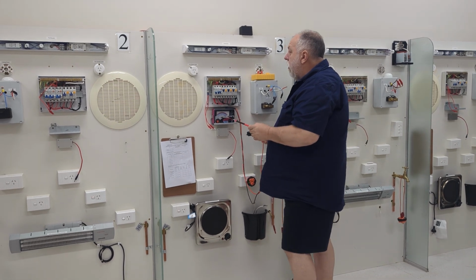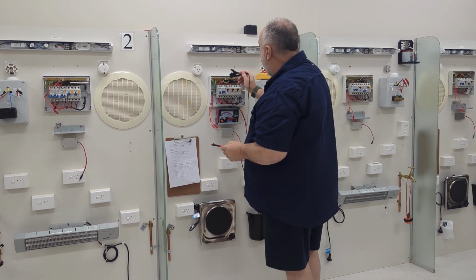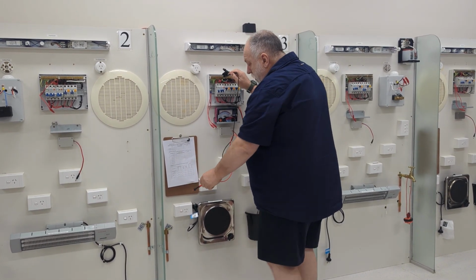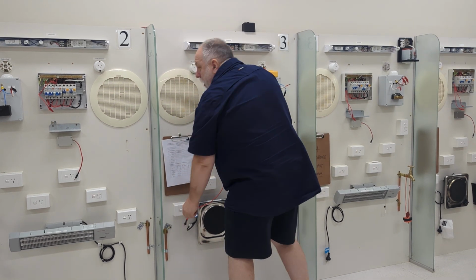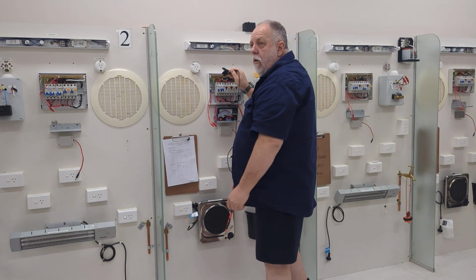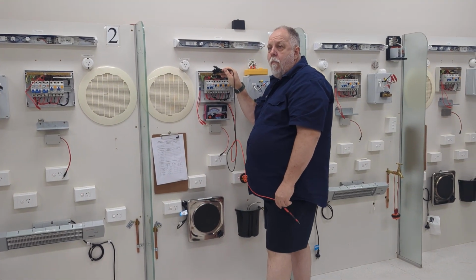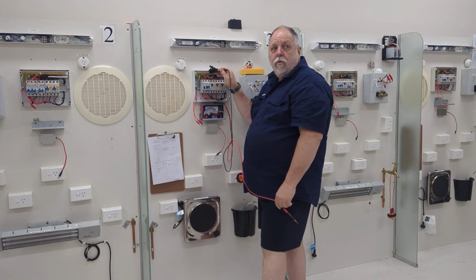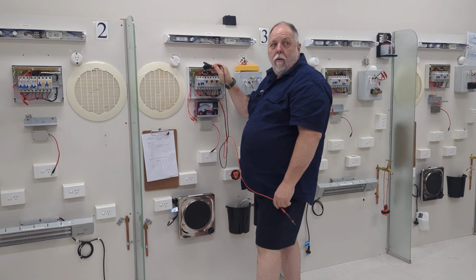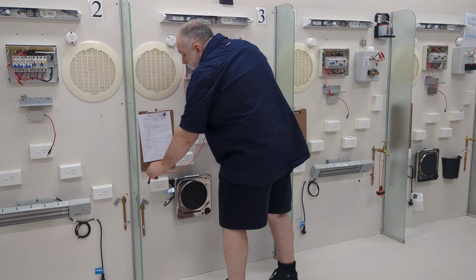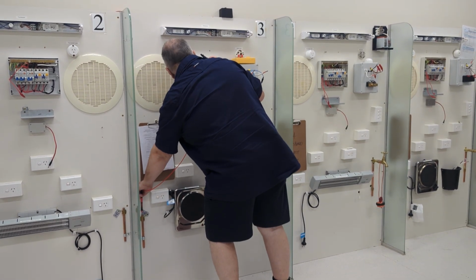The first test I'm going to do is go from my main earth down to my earth stake. Do not go to the clip. Why don't I test to the clip? Because that's not the part that's in the ground. That's exactly right. So I need to test to the earth electrode.